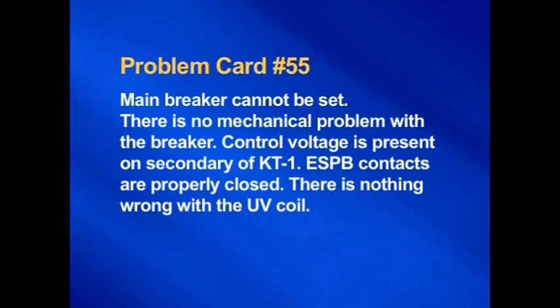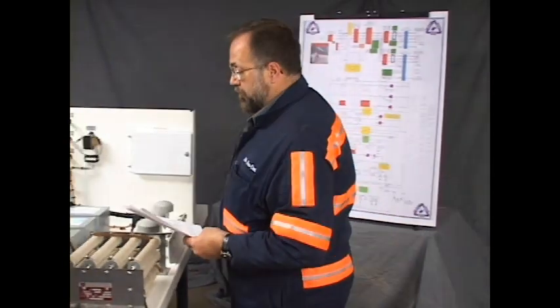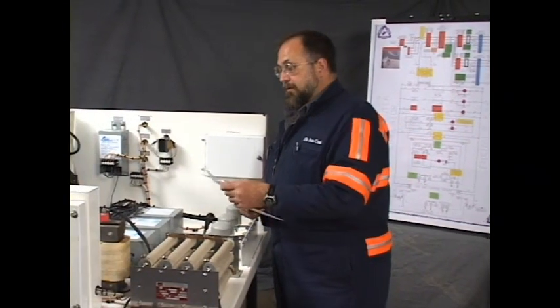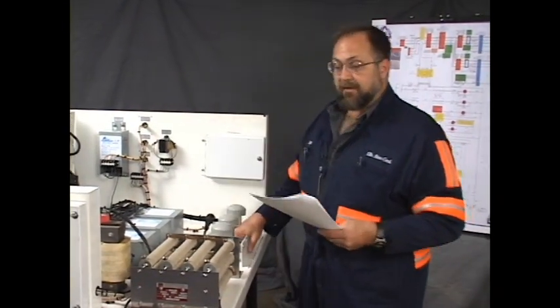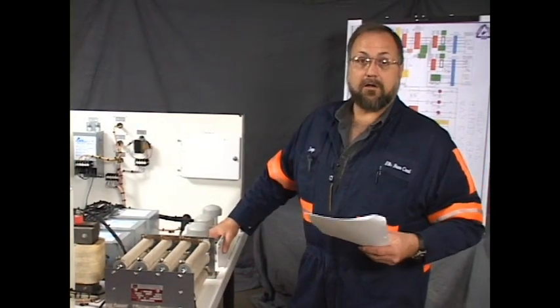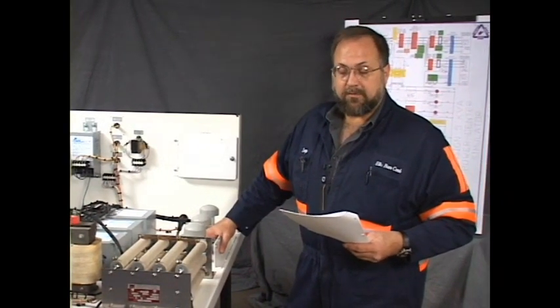Okay guys, so this is problem number 55. The main breaker cannot be set. There's no mechanical problem with the breaker. Control voltage is present on the secondary of KT1. ESPB contacts are properly closed. There's nothing wrong with the UV coil. Again, the problem they give you, although it tells you one thing that can't happen, it tells you a lot of things that are happening. It narrows the field a bit for you.